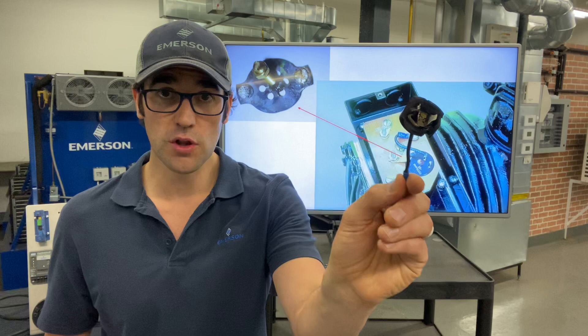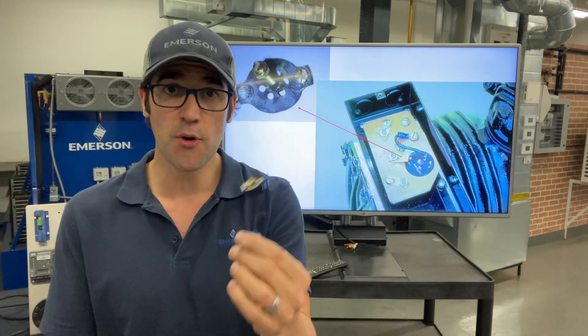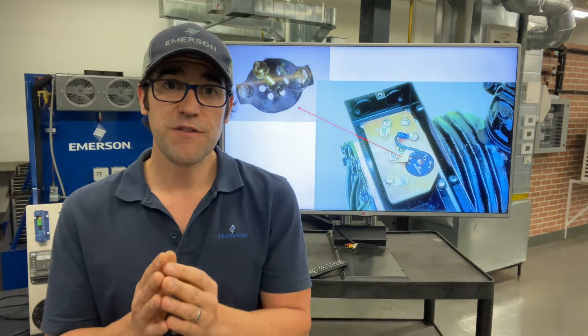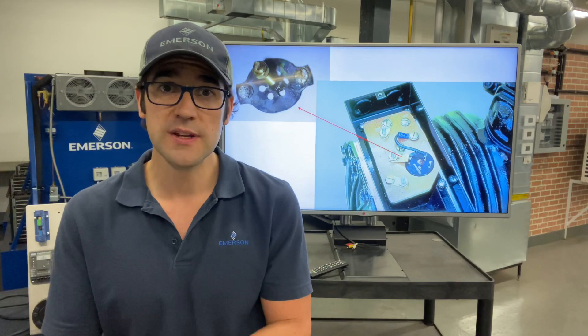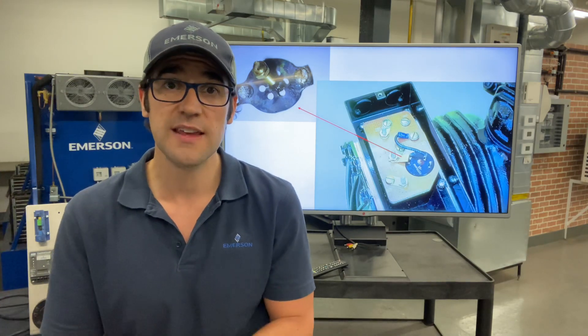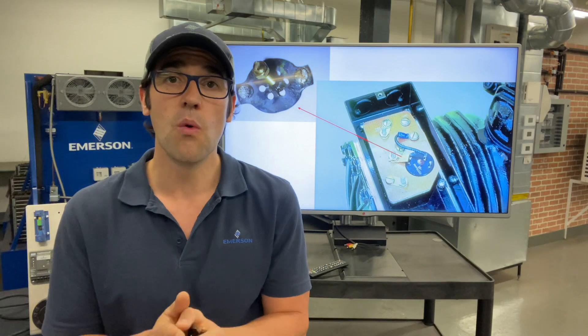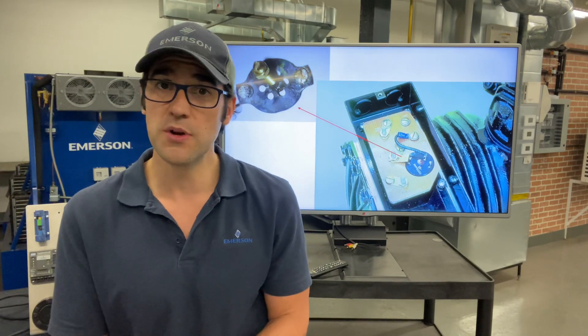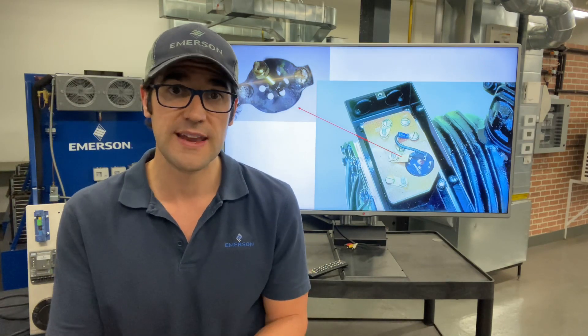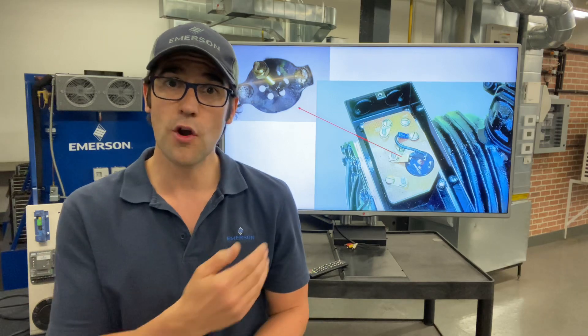I have one here. I pulled this out of a K body. I broke it open to look at it. If you have compressors tripping off you need to take the time. He feels technicians aren't taking the time to deep dive to figure out what caused that failure because when you put another compressor in and you don't find the failure, that next one's gonna fail and this one's an overheat situation.